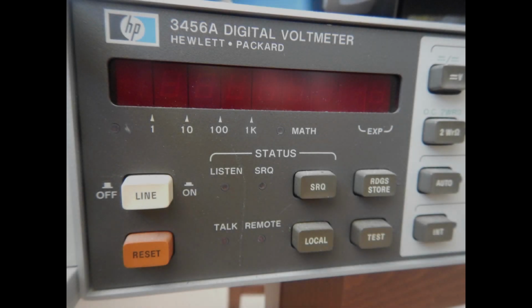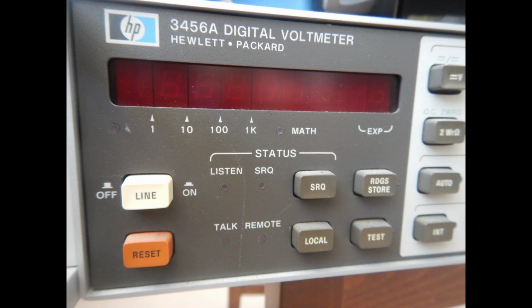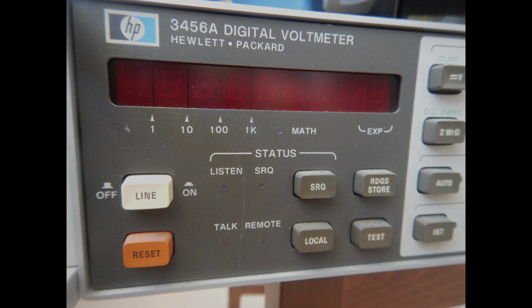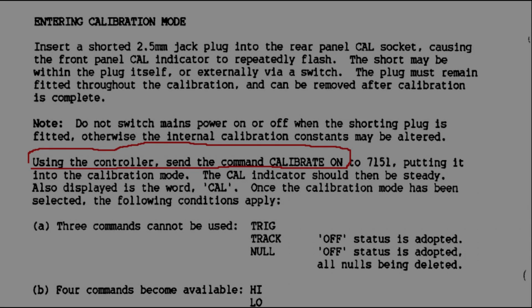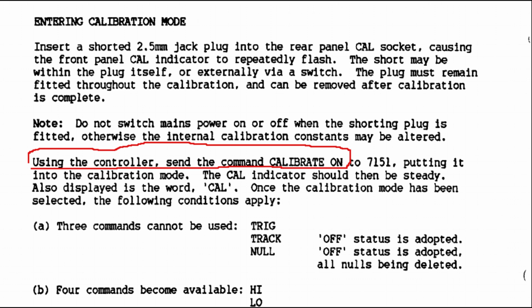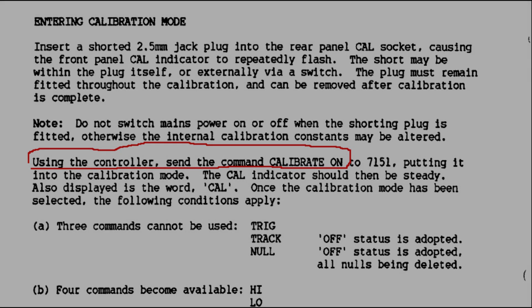At this point, to discover if there are other hidden faults with this multimeter, or even to be able to use it regularly, I should attempt a complete calibration. Unfortunately, I don't have any calibration source stable enough for such a multimeter. However, I could try to calibrate it against my HP 3456A multimeter, which has been very stable in these years, and anyway, it's really all I can do. However, part of the calibration procedure of this multimeter is carried over the IEEE 488 interface, or GPIB, so I need to verify that the interface is working fine first.